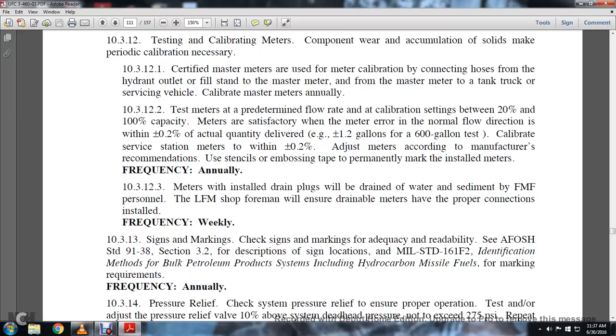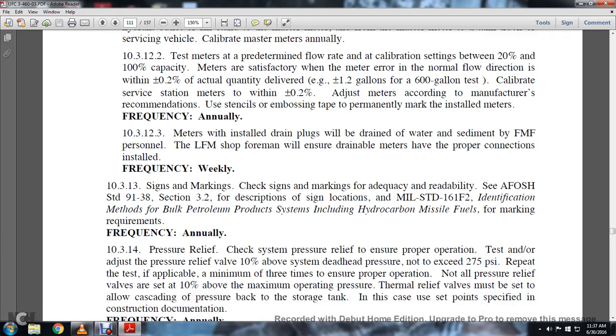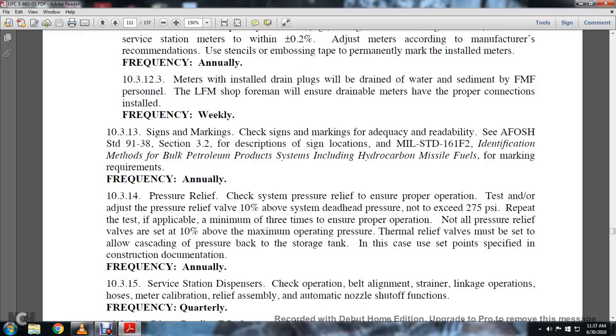10-3-13 Signs and markings. Check the signs and markings for adequate readability. See AFOSH 91-38 section 3.2 for description of the sign location. Military Standard 161-F, Identification Methods for Bulk Petroleum Products Systems, including hydrocarbon missile fuels, for marking requirements. Frequency: annually. The pressure relief. Check the system for pressure relief to ensure proper operation.